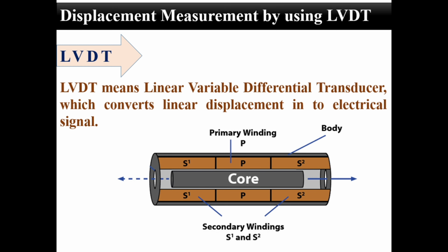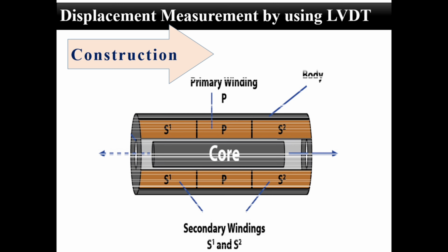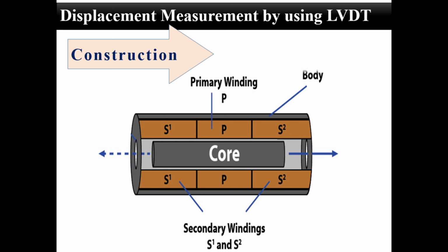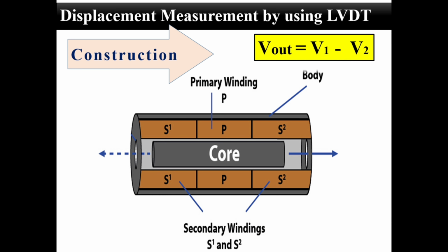Now let's see its construction. LVDT consists of one primary winding P and two secondary windings S1 and S2 mounted on a cylindrical former, as shown in this figure. Both secondary windings, S1 and S2, have an equal number of turns and are placed identically on either side of the primary winding, such that the net output will be the difference of voltage induced in both secondary windings, that is, V out equals V1 minus V2.